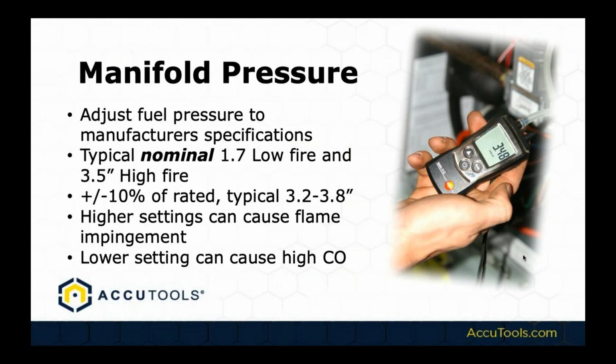And we do that by getting the manifold pressure correct. And a lot of guys are always like, oh, you've got to set it to exactly 3.5 inches of water column. Well, that is a nominal fuel pressure, okay? So it's a nominal fuel pressure, which means the standard fuel pressure that the system's designed with. And that means it's designed for that gas pressure at a certain heat content of fuel, which we don't typically know from the manufacturer. A lot of times it's a higher heat content, like 1070 BTUs. But without clocking a meter, we just don't know.